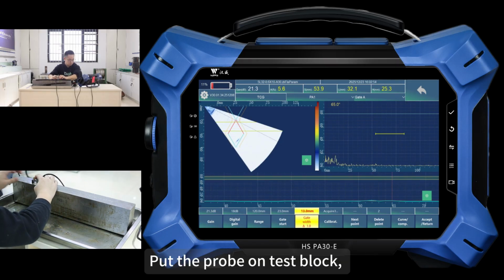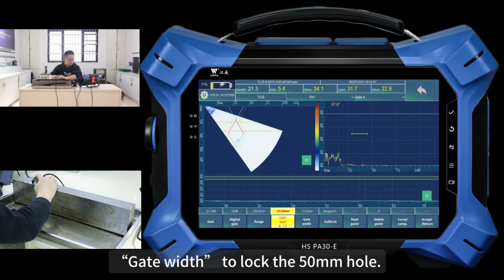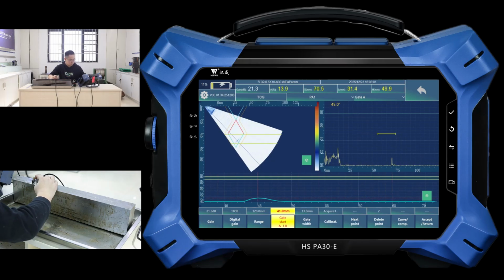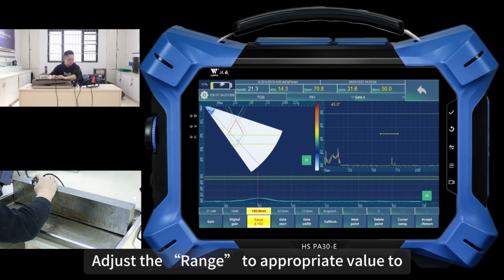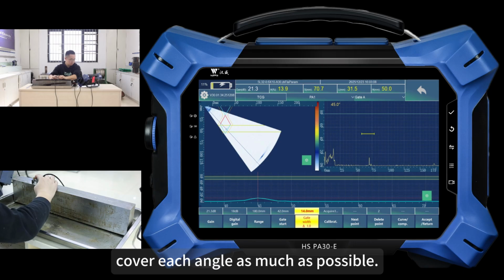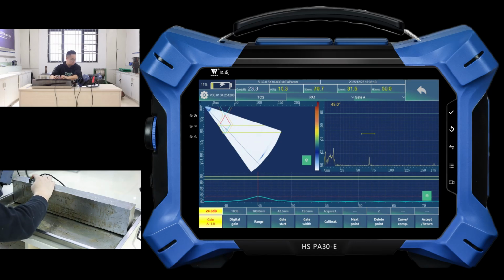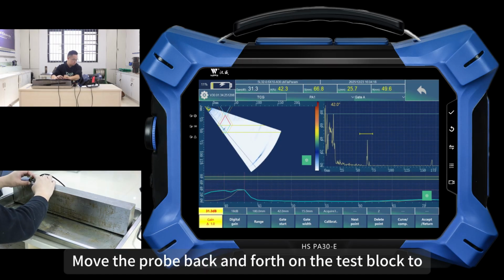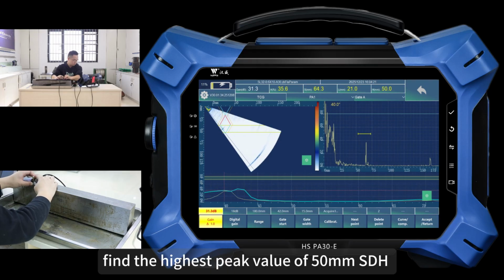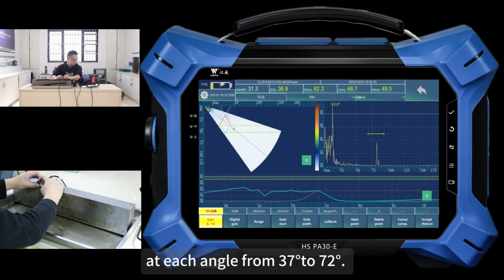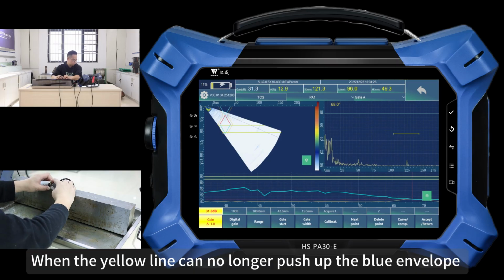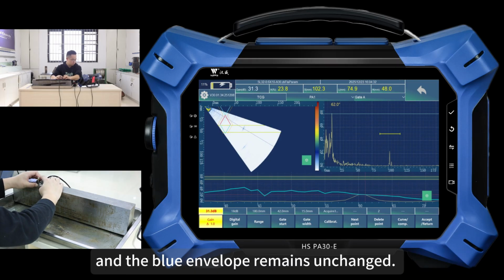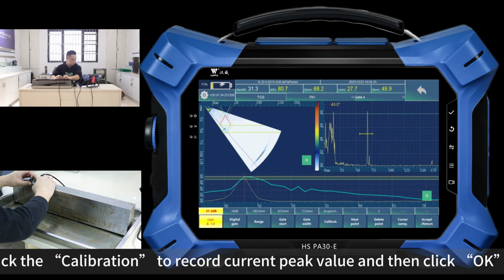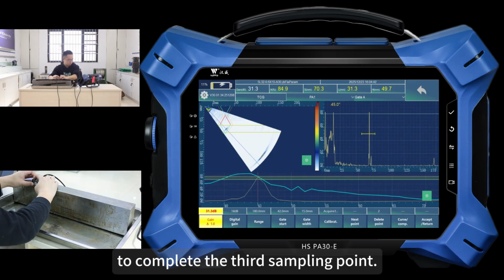Put the probe on the test block. Adjust gain, start, and gate width to lock the 50 mm hole. Adjust the range to an appropriate value to cover each angle as much as possible. Adjust the gain value. Move the probe back and forth on the test block to find the highest peak value of the 50 mm SDH at each angle from 37 to 72. When the yellow line can no longer push up the blue envelope, and the blue envelope remains unchanged, click Calibration to record the current peak value and then click OK to complete the third sampling point.